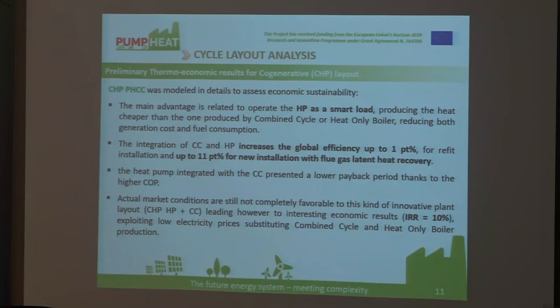The main advantage of this layout is to operate the heat pump as a smart load, producing heat from electricity when it's cheaper than from the combined cycle or heat-only boiler. We can increase global efficiency by about 1% for existing systems, and up to 11 percentage points for new installations with flue gas latent heat recovery—meaning we must change something in our heat recovery steam generator.